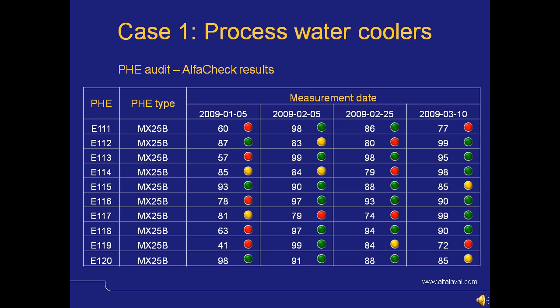In this case, for example, number E111, it had gone from 60 to 98%, meaning that it was cleaned well, and then it started to deteriorate a little bit, but it's only a couple of percentage.